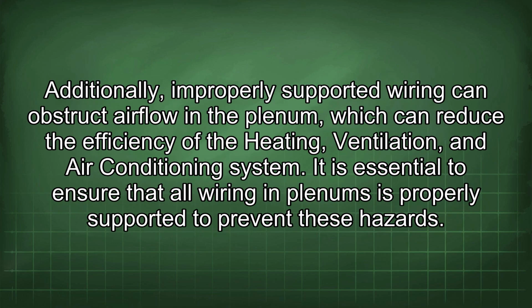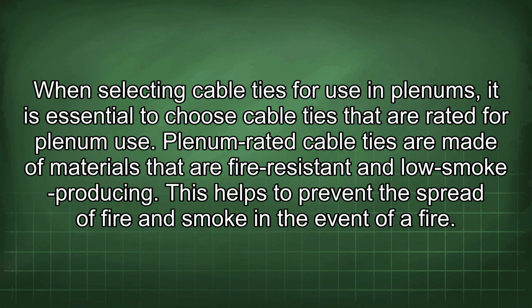Additionally, improperly supported wiring can obstruct airflow in the plenum, which can reduce the efficiency of the heating, ventilation, and air conditioning system. It is essential to ensure that all wiring in plenums is properly supported to prevent these hazards. When selecting cable ties for use in plenums, it is essential to choose cable ties that are rated for plenum use. Plenum-rated cable ties are made of materials that are fire-resistant and low smoke-producing. This helps to prevent the spread of fire and smoke in the event of a fire.